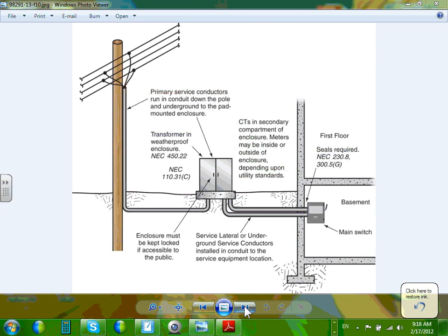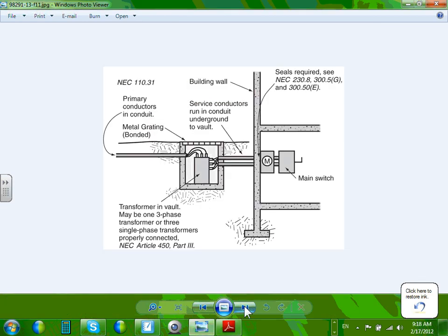Okay, so that could be your service at the bottom here. That could be your service entrance conductors or service lateral, depending upon where you put your service point. And we're going to talk about service point, it is very important. The first thing when you become a project manager, guys, you have to ask about is the service point. Look at this underground. The same thing. This is most likely in downtown Minneapolis and all this stuff. They come with the high voltage to a transformer in a vault, and from the transformer they go to the building. Can you guys see where the meter is sitting right here inside the building with the main disconnect?